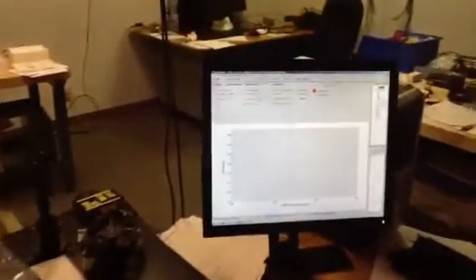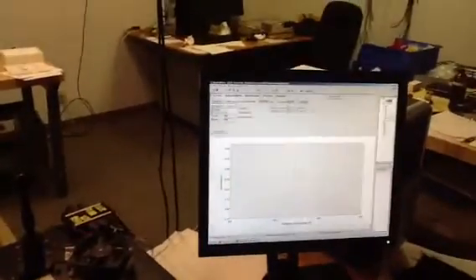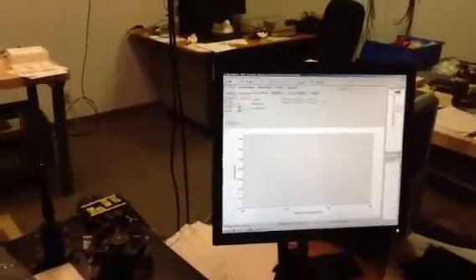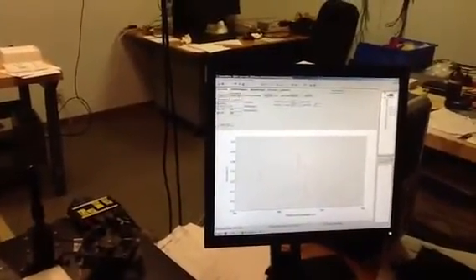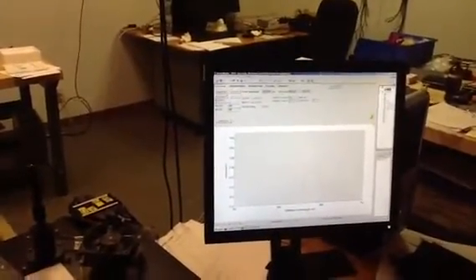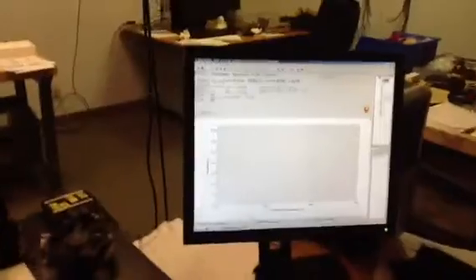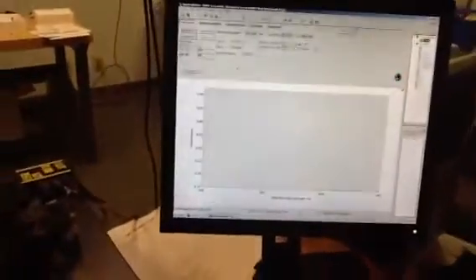This spectrophotometer will collect at a normal scan rate, and actually there's the result already. That's the holmium oxide filter spectrum we're collecting, but here we're doing it in real-time.